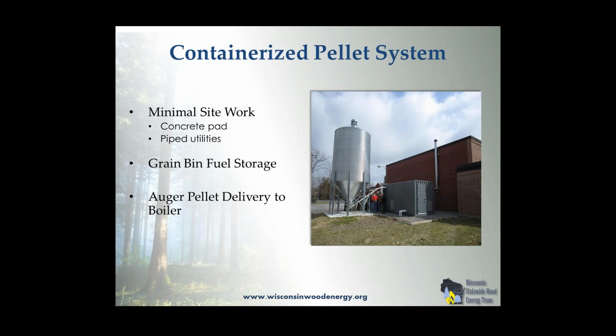Containerized systems, whether it's cordwood or pellet systems, they really minimize the development costs. You kind of cut the engineer out of the equation. You make it so that the development cost of a project is minimal. And also, you cut down a lot on the time. So the pellet system you look at here is in a shipping container. It's just dropped off on a pad. You plug in the water supply and return, you supply potable water into the system, you pipe your pellets into the boiler, and it's all self-contained in one unit.